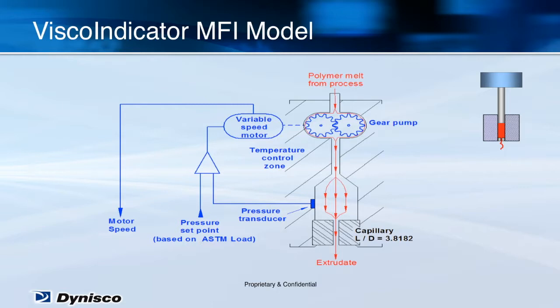In the model of the visco indicator you can see on this slide, a side stream is taken from the extruder as indicated by the red text at the top center. Process pressure from the extruder forces polymer melt into a metering gear pump. The pump then generates the flow rate and pressure to extrude the polymer through a capillary. The temperature of the steel around the capillary and the pump is controlled, and a single pressure transducer is located above the capillary to measure driving pressure. The test polymer extrudes to atmosphere. By that I mean it falls to the floor, just like it would in the melt flow indexer. All material that enters the rheometer flows out as scrap, typically at the rate of 1/2 kilogram per hour. This rheometer duplicates the internal geometry of the melt flow indexer, so the capillary entrance effects are similar.